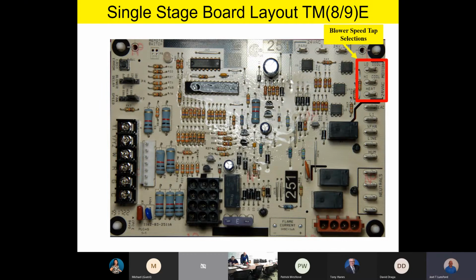Any questions or comments so far on the motor speed taps and the basic idea that this board, even though it's a single stage heating board, we can literally hook it up to any of our 2-stage equipment as well, and even our 5-stage TH16 5-stage heat pump as well on a dual fuel? Any questions or comments on that?